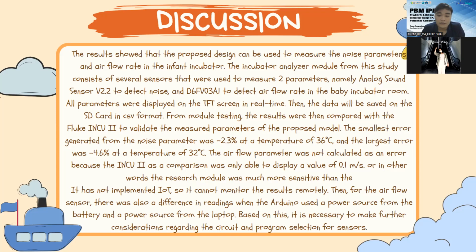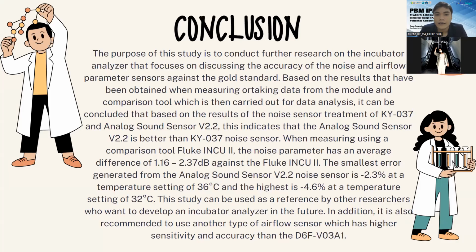Okay, based on this, it is necessary to make further consideration regarding the circuit and program selection for the sensors. Then the conclusion: the purpose of this study is to conduct further research on the incubator analyzer that focuses on the accuracy of the noise and airflow parameter sensors against the gold standard.